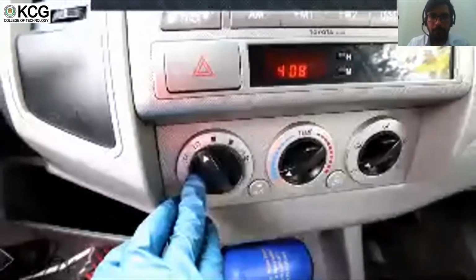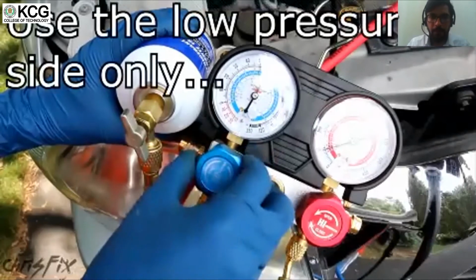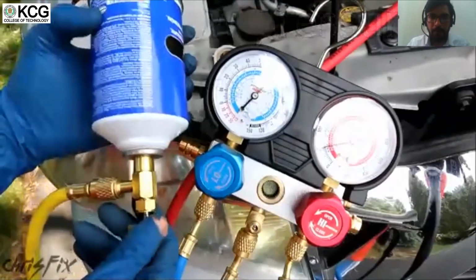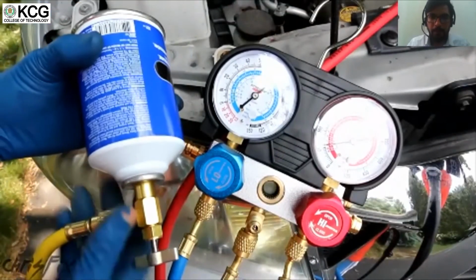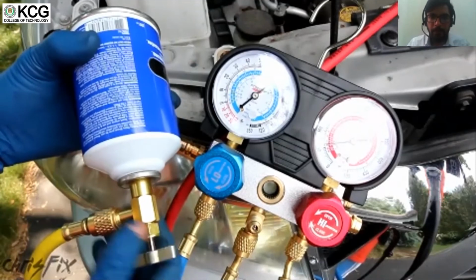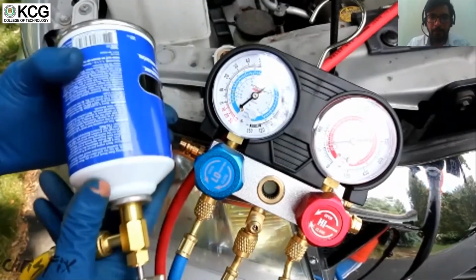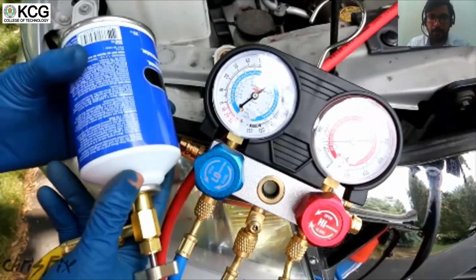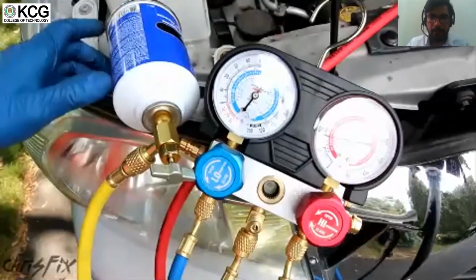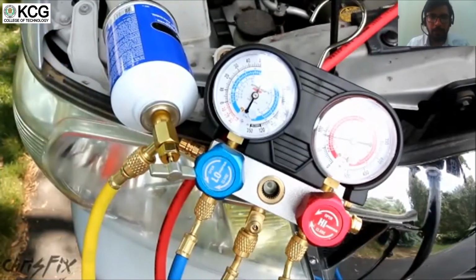Next, open up the valve on the low pressure side of the manifold gauge. Now refrigerant is flowing into the system. I'm going to put this down on a cool part of the engine compartment, but you don't want to put this down on anything hot because it could heat up the can and cause an explosion, which would not be good. Now we just wait for the compressor to kick on. Perfect. It just kicked on.